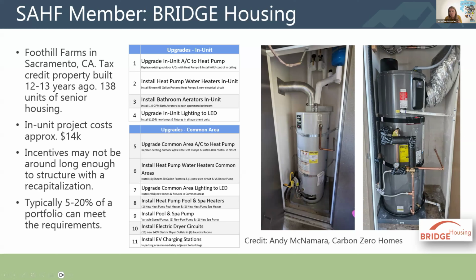One reason Carbon Zero Buildings and Bridge were able to make it happen so successfully and quickly is that they did a one-unit mock-up to test switching from the gas water heater to a heat pump water heater. This let them confirm there were no problems on the electrical side or in switching out that indirect heating, and all the things that needed to be done. By doing that and phasing the work across the 138 units, they were able to set it up so they could do one unit a day.